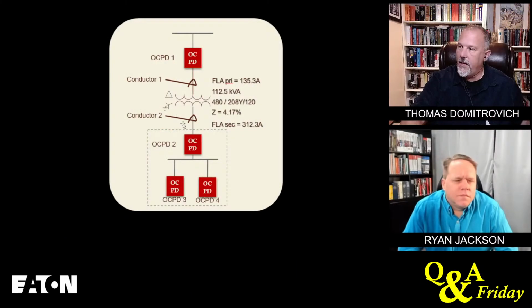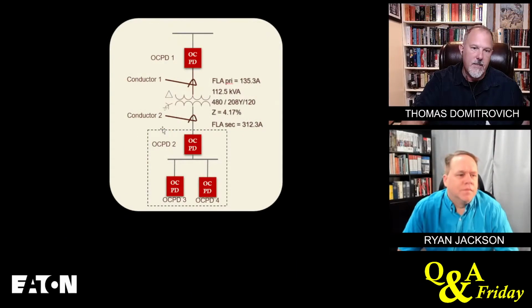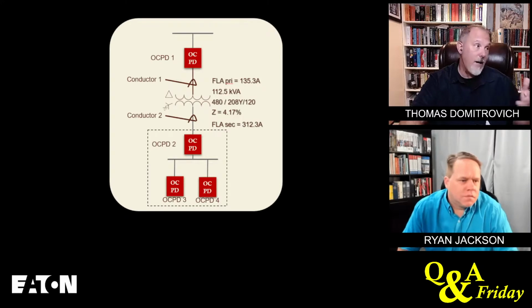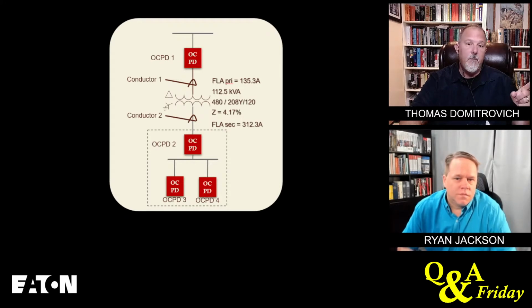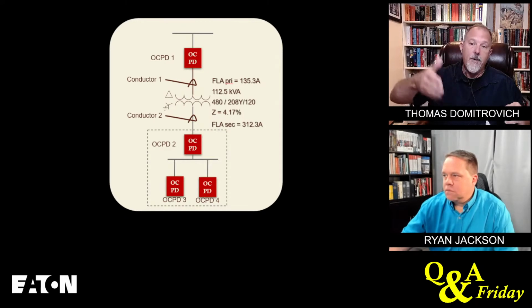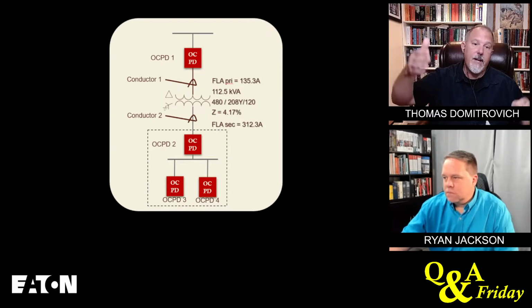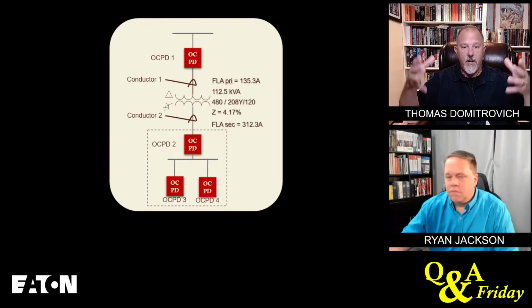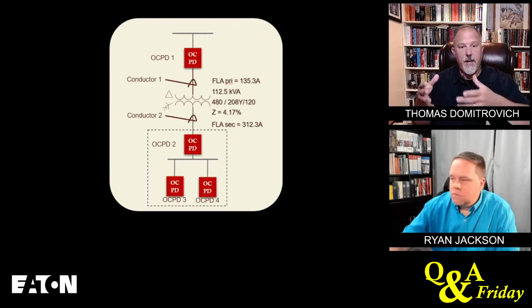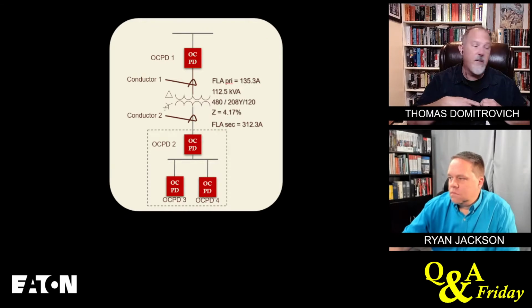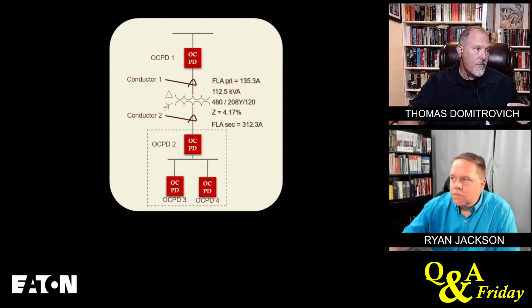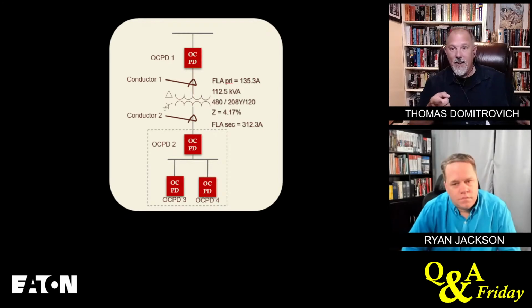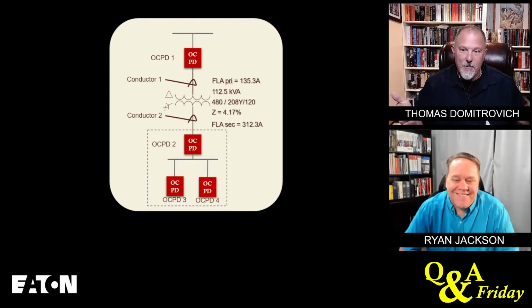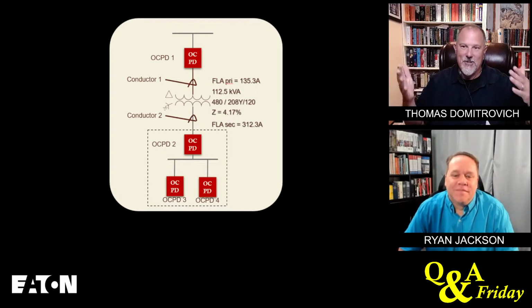So there's an NEC requirement that says when you have, or actually it's going to be a 2023, and I got to find the section number, but it talked about requiring barriers on the secondary for that panelboard or whatever is being supplied on the secondary of that transformer to barrier off the line side lugs. And the problem was, and you pointed it out, as well as Palmer Hickman, and Palmer called me about it, and he's like, help me understand this.